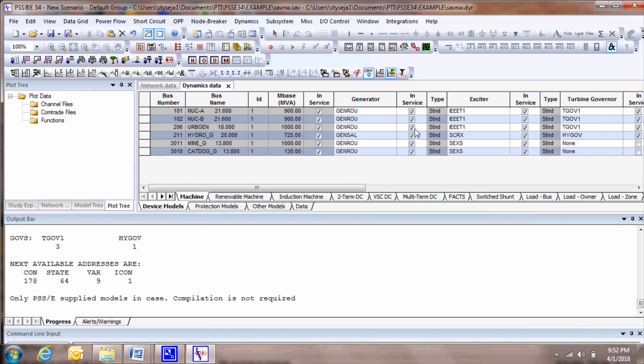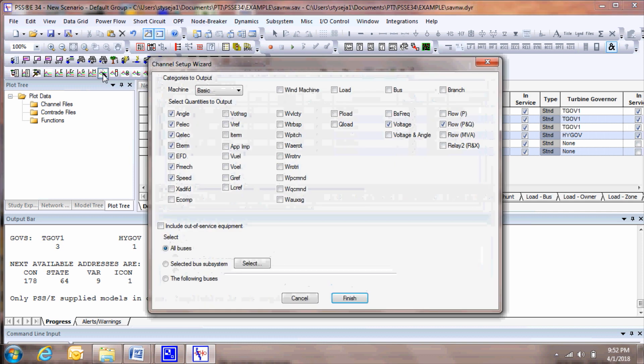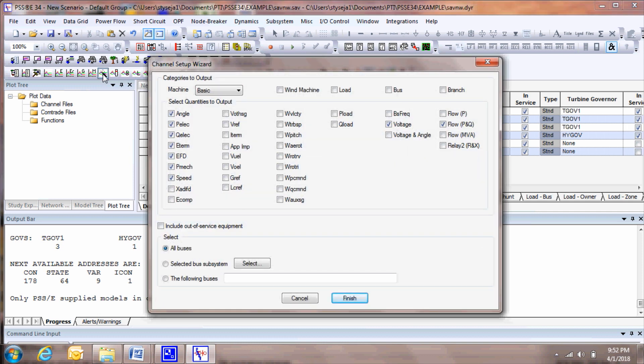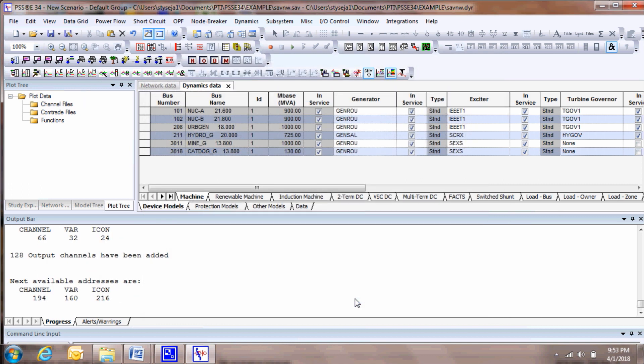You can now conduct the dynamic simulation. Before you do this, you may want to define the plot variables to be viewed after carrying out a dynamic simulation. One quick and easy way to add the plot quantities is to open the Channel Setup Wizard and select the quantities you wish to plot. For the purpose of this example, we'll select All Buses and click Finish. All plot quantities are added to the dynamic case.